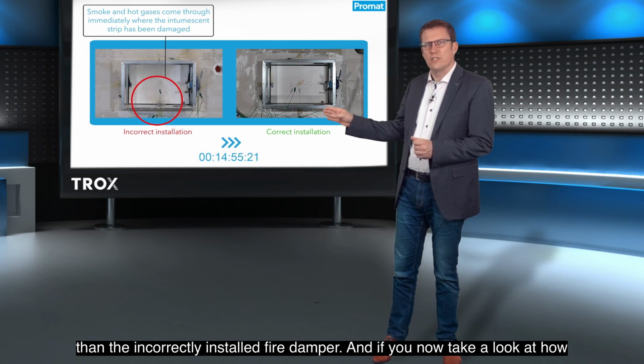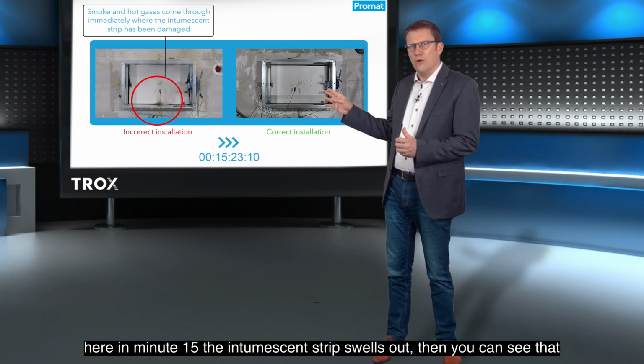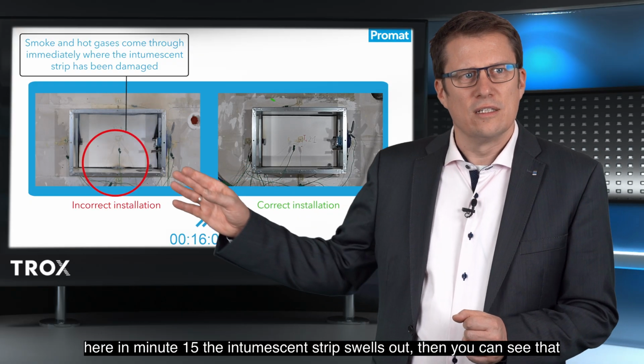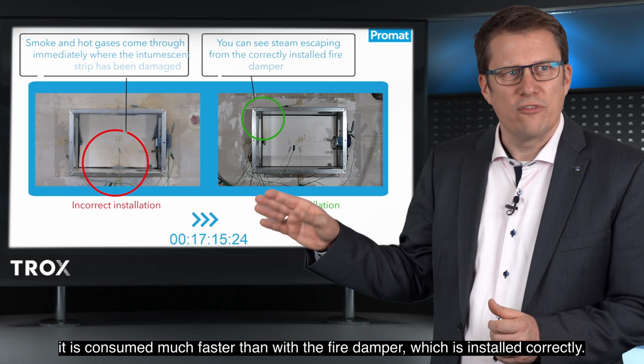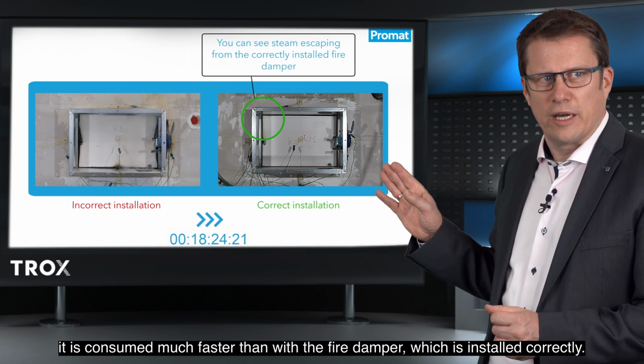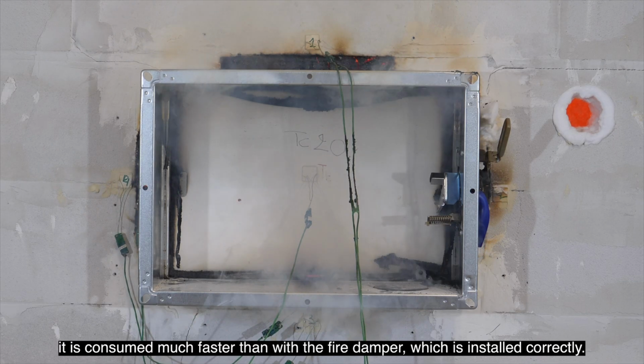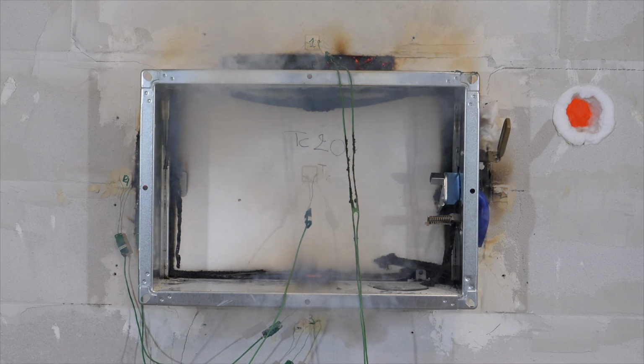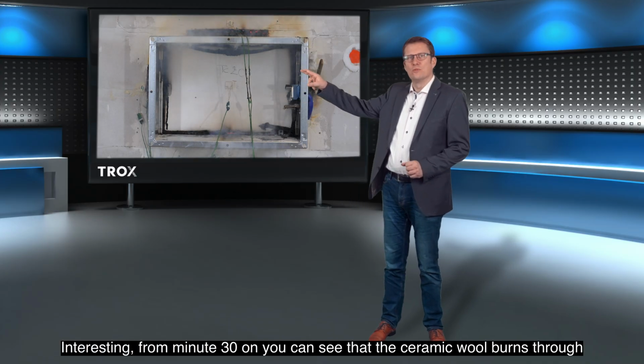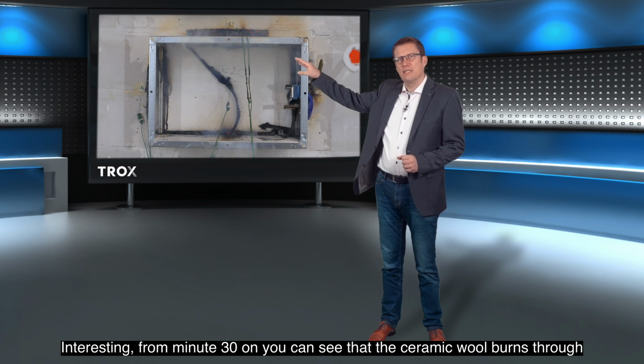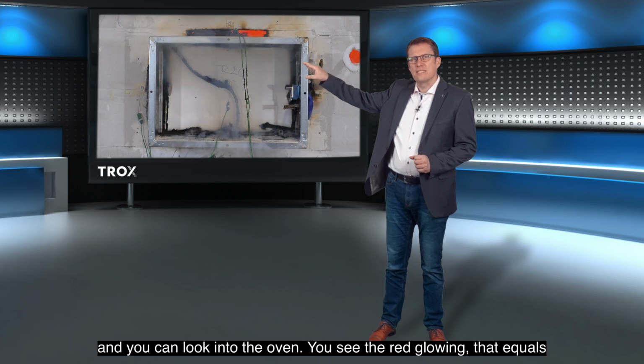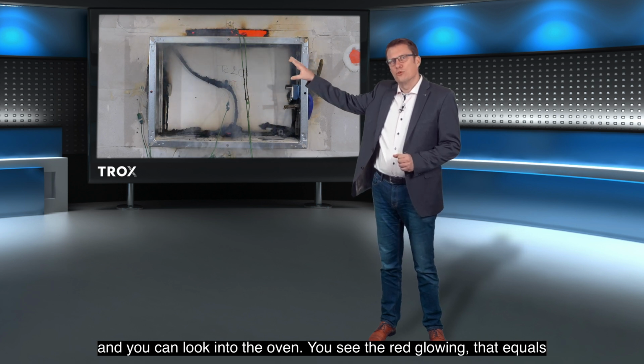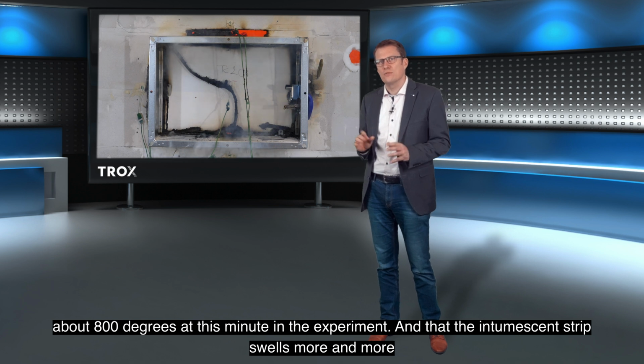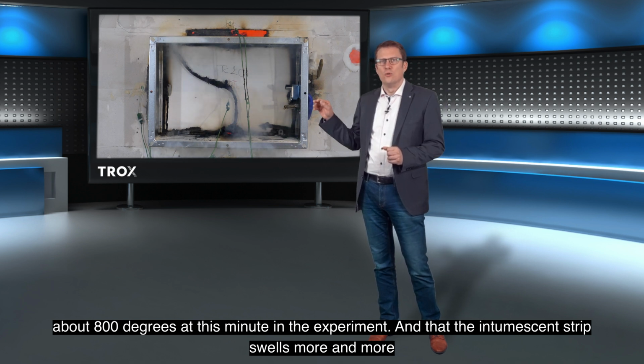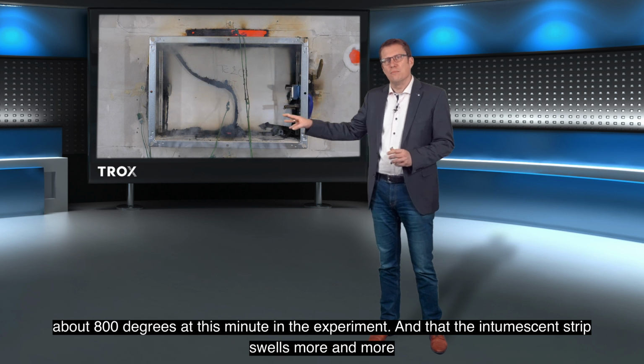And if you now take a look at how here in minute 15 the intumescent strip swells out, then you can see that it is consumed much faster than with the fire damper, which is installed correctly. Interesting, from minute 30 on you can see that the ceramic wool burns through and you can look into the oven. You see the red glowing that equals about 800 degrees at this minute in the experiment, and that the intumescent strip swells more and more from these temperatures.